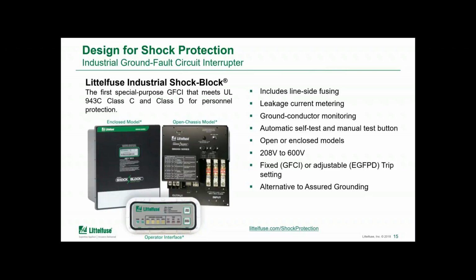If you go back to the hierarchy of controls, a special purpose GFCI provides you with a safer substitute for the Assured Grounding Program, and for all applications provides an engineering control in terms of the actual ground fault detection to reduce the risk of shock. Now, if you're considering industrial shock protection, it's worth checking the standards that the products are tested to. The term GFCI isn't truly legally protected. So even if the product is called a GFCI, it's important to look at the UL listing and make sure it is listed to the right standard, so that you know what you're getting and the product is going to behave as you expect. There's more information available on these devices at the link shown on the screen.